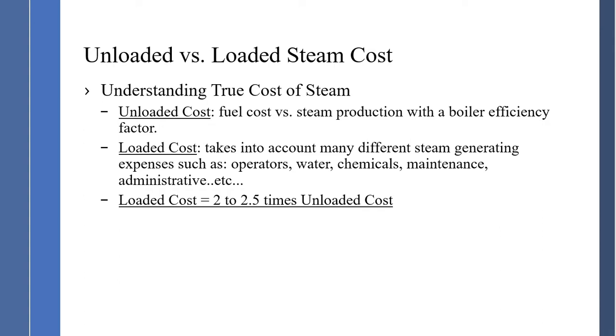Understanding unloaded and loaded costs — loaded costs take in all steam generating expenses: operator, water, chemical, maintenance, administration, all aspects of operation. So if we calculate out $5.40 as the unloaded cost, loaded costs are usually two to two-and-a-half times that unloaded cost, which would be almost $10 — over $10 per thousand pounds of steam.